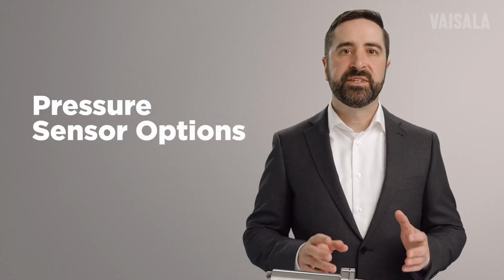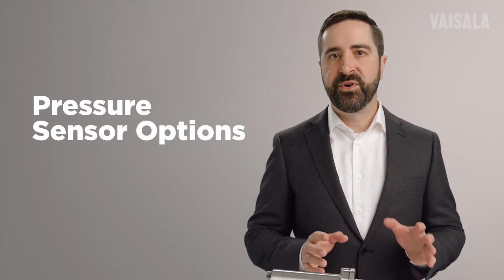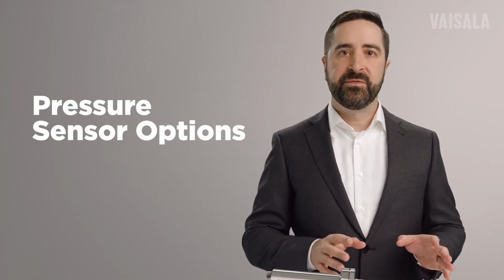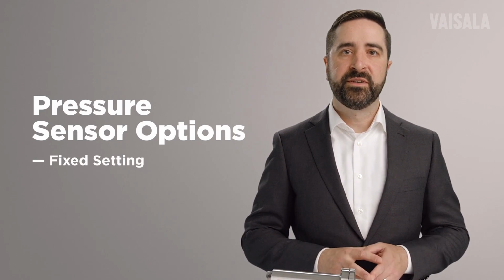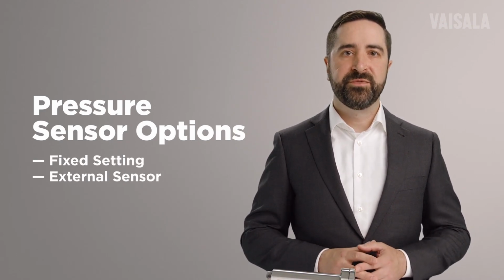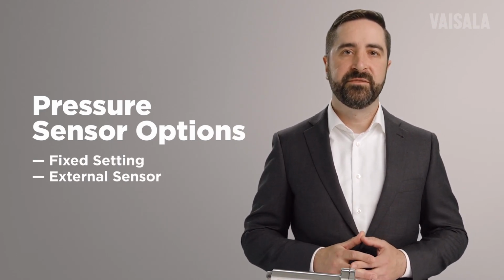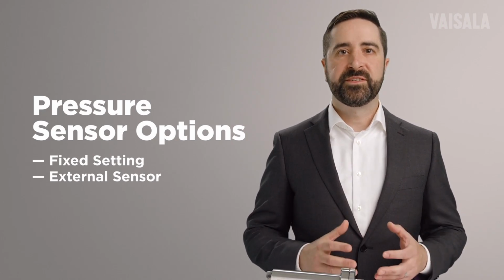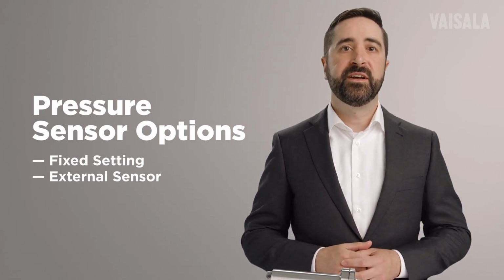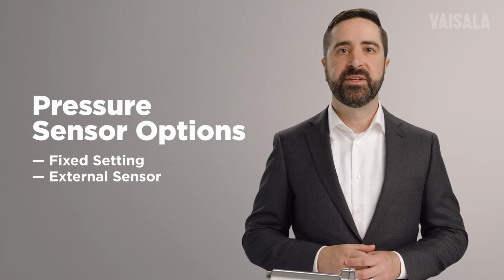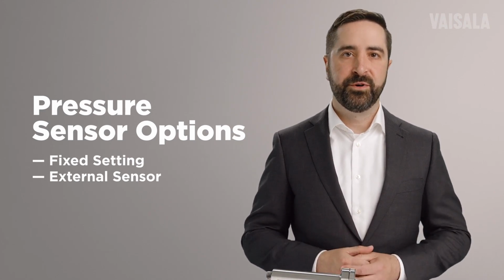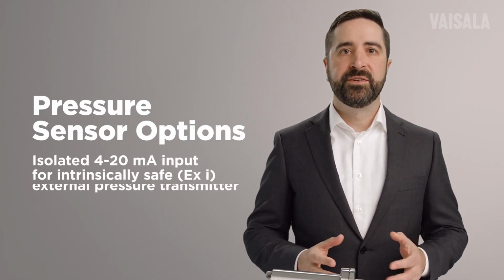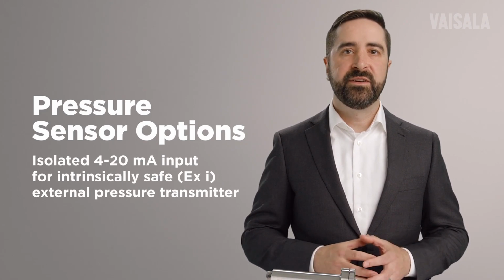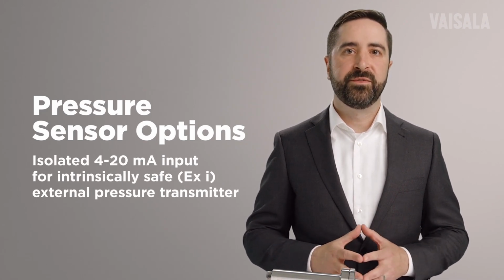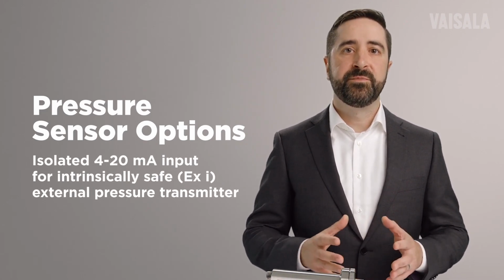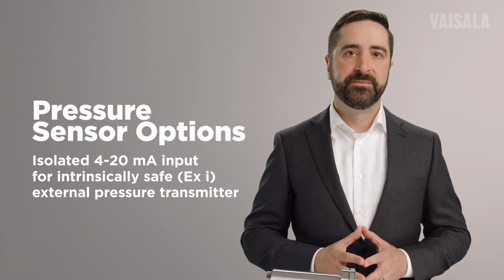The MGP 260 series do not have an onboard pressure measurement, so you'll configure with either a fixed pressure set point or have the probe receive a pressure reading from an external pressure sensor that is installed nearby. For maximum accuracy, it is recommended that an external pressure sensor be installed in the gas stream and connected to the probe. Both models include an isolated, EX-rated 4 to 20 milliamp input for a pressure sensor. This input will power the sensor as well.